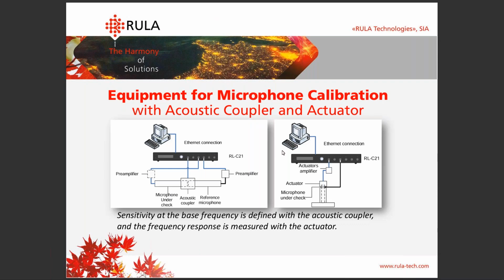Yeah, there is another way you can perform calibration of a microphone, and it's a slightly different set. You could use an acoustic coupler in order to define the sensitivity at the base frequency. And then at the next step, you can measure the frequency response with the actuator.